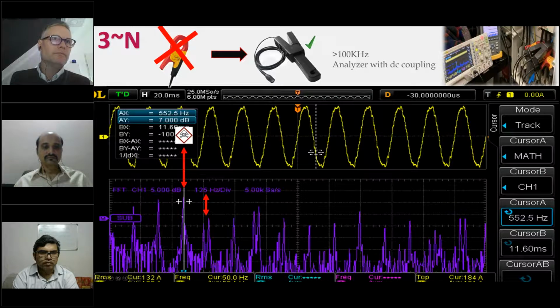What I saw over there, here you can see we have 550 hertz, that's this one, so that's the 11th harmonic, and it's jumping up and down, up and down, up and down. When you let your oscilloscope make a snapshot, it will calculate the amperage - the nominal, the big signal is 130 amps per phase. When you divide that, you will see it's about 5 or 6 amps at 550 hertz.